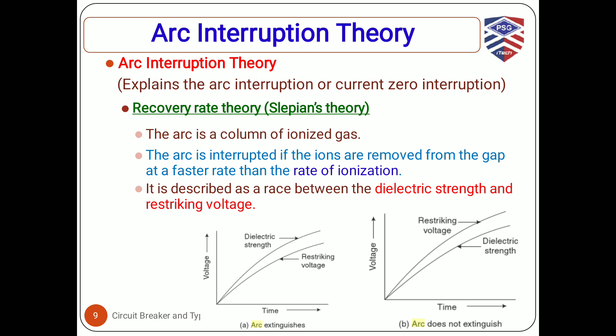As you can see from the first diagram, regarding the dielectric strength of the medium connecting the fixed contact and moving contact of the circuit breaker, the arc can be quenched only if the dielectric strength is more than the restriking voltage. Just recall what the restriking voltage is. It is the transient voltage that appears across the circuit breaker contacts at the instant of arc extinction. So it is going to be a huge oscillating voltage. If the dielectric strength of the medium is more than the restriking voltage, definitely the arc can be quenched immediately. If the restriking voltage is more than the dielectric strength, meaning the dielectric strength of the medium is poorer than the restriking voltage, it will not be able to quench the arc.